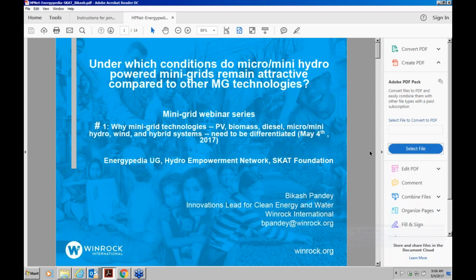That is correct, but we see both these days, especially with the availability of pipes and smaller pipes that are mass manufactured, a tendency to use pipe. Sometimes we've seen penstock pipes as long as 2-3 kilometers because the cost of civil works can be quite high, especially in remote areas. It's actually cheaper to carry pipe than to carry cement and bring up sand, and all these types of construction can be quite expensive. So where there are no roads, in places like Nepal we see a tendency nowadays to use more pipe, and indeed use that option of just a pipe all the way.